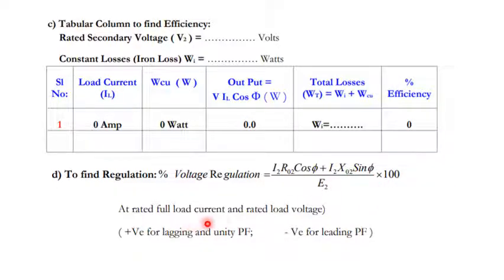At rated full load current and rated load voltage, if you get a positive percentage voltage regulation value, what does that mean? This is a lagging power factor or unity power factor. If you get a negative value for this load condition, that is full load current and rated load voltage, what does that mean? This is a leading power factor.